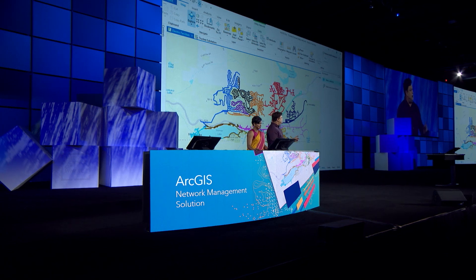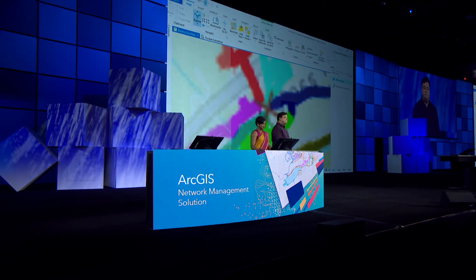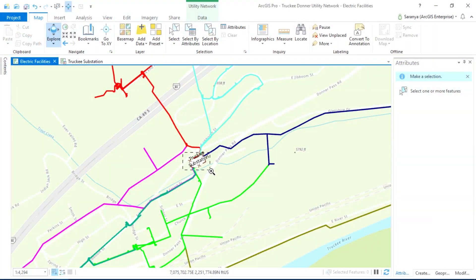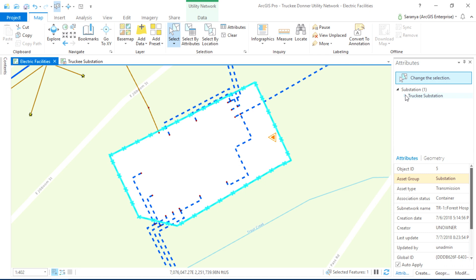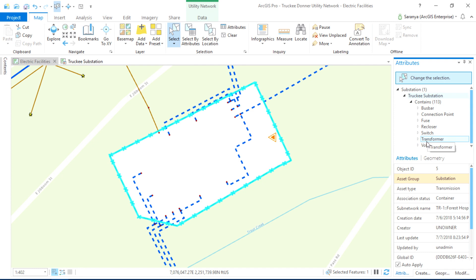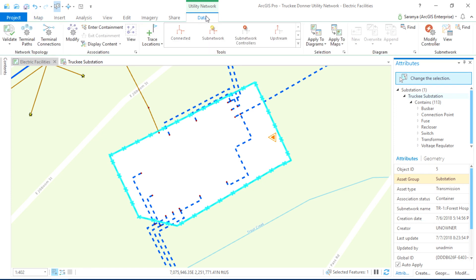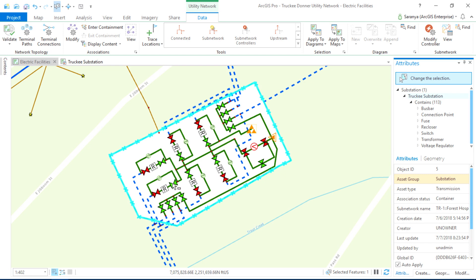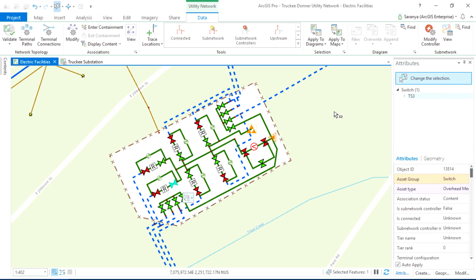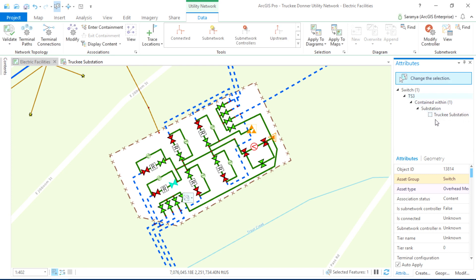Number one: modeling data in more detail. Taking a look at this circuit map, substations in general are kind of like a network inside a network, and maybe not so often represented in GIS. But here we could select the substation, and the attribute values show all the equipment in it. What's more, we can go into Containment and see the features on a map. Now we can trace from our circuits through the substation down to the customer.